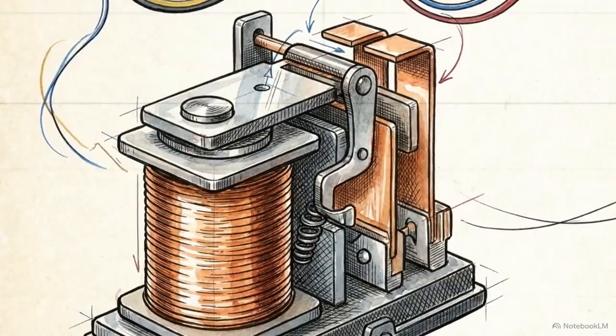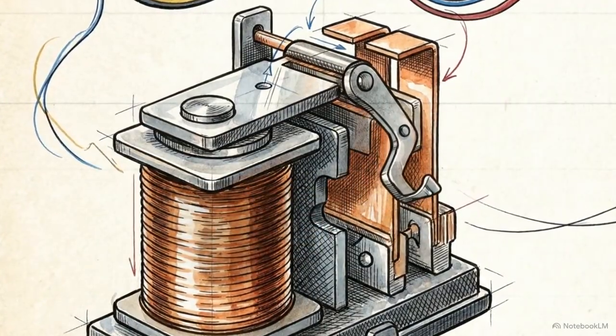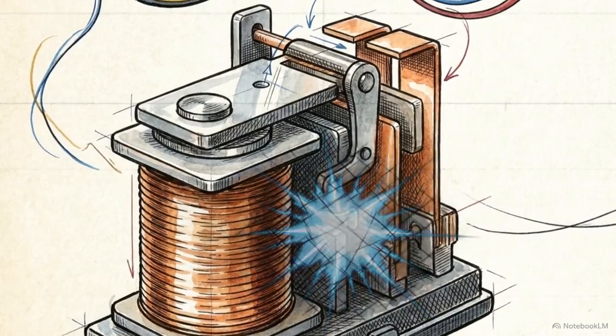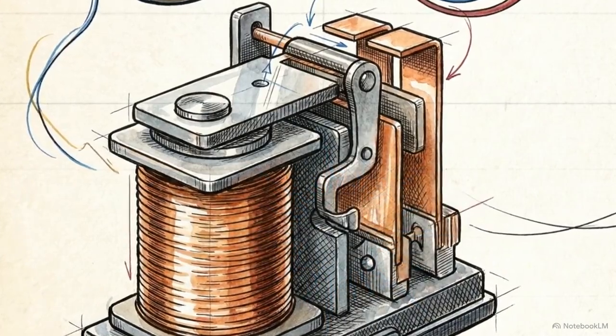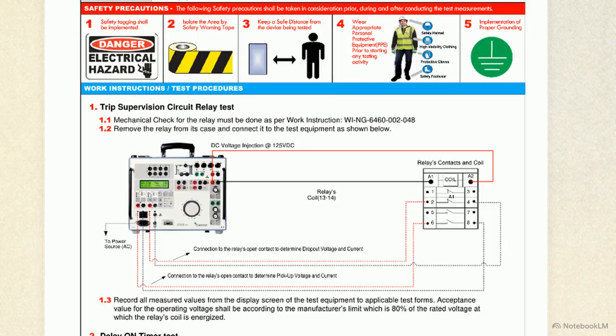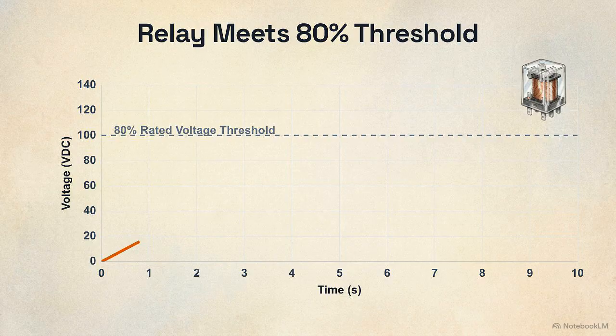Copper pathways only function if the panel knows when to open or close them. Supervision relays provide this logic and must trigger exactly on command. This diagram illustrates a secondary injection test. A variable DC voltage source connects directly to the relay's internal coil at terminals 13 and 14. The technician increases the voltage to pinpoint the pickup threshold required to physically close the contact. The recorded pickup voltage must align with the manufacturer's established limits.